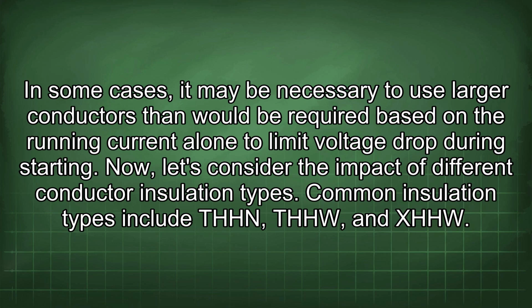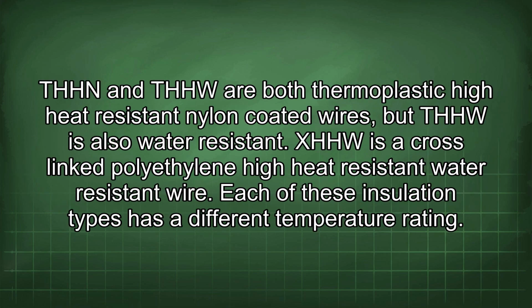Now let's consider the impact of different conductor insulation types. Common insulation types include THHN, THHW, and XHHW. THHN and THHW are both thermoplastic high heat resistant nylon coated wires, but THHW is also water resistant. XHHW is a cross-linked polyethylene high heat resistant water resistant wire. Each of these insulation types has a different temperature rating.